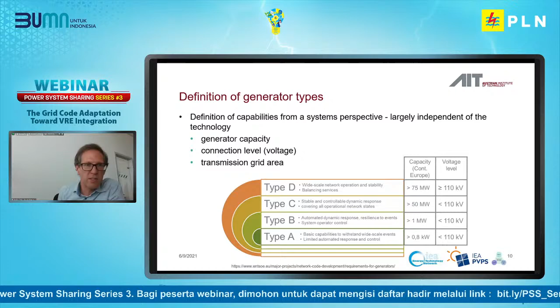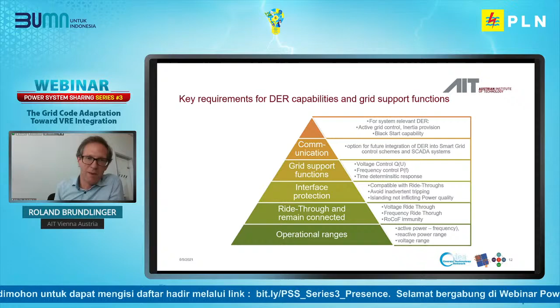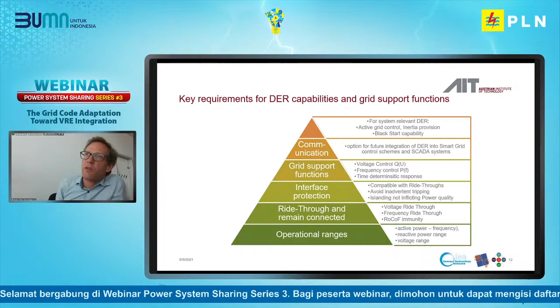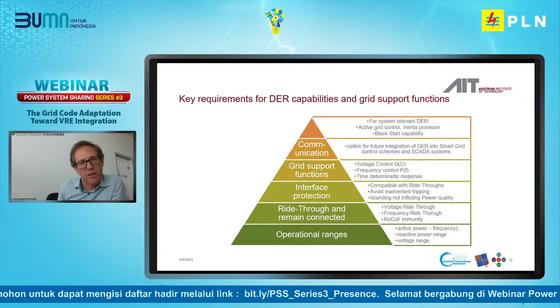Now coming to the second part of my presentation, the grid support functions. In our work, we have put together this pyramid model, which allows us to structure the requirements. On the fundamental base, the requirements in the grid codes define operational ranges for active power, frequency and voltage. Based on these fundamental ranges, there are additional requirements for ride-through capabilities and remain-connected capabilities, where conditions are defined in which the generator is not allowed to disconnect from the system.